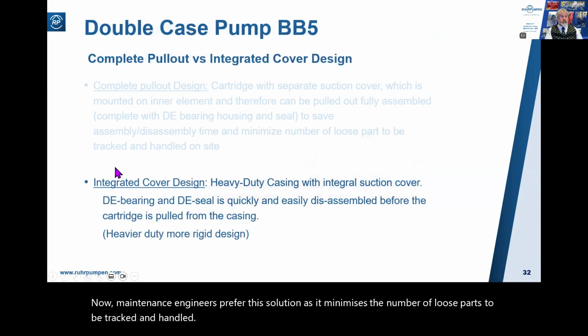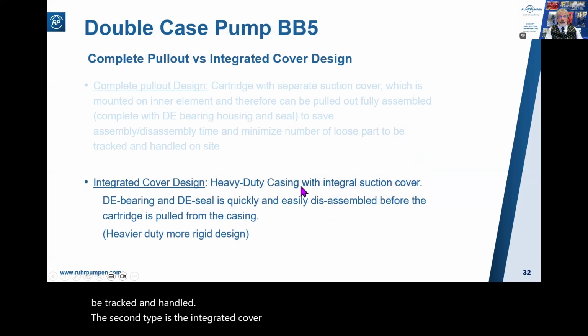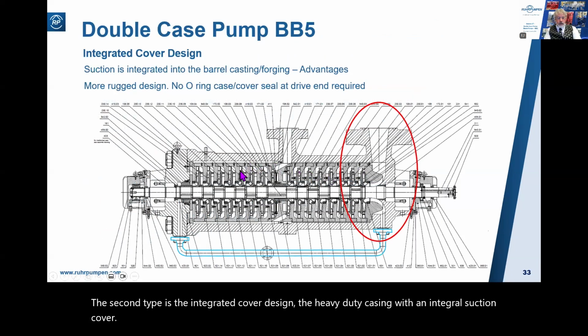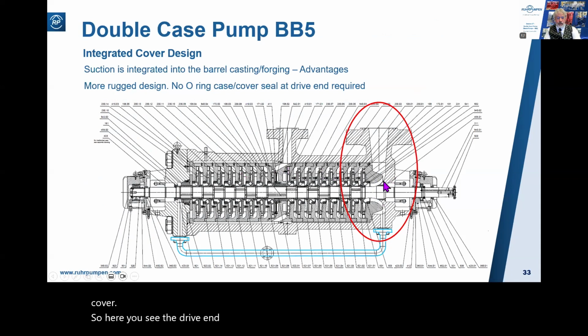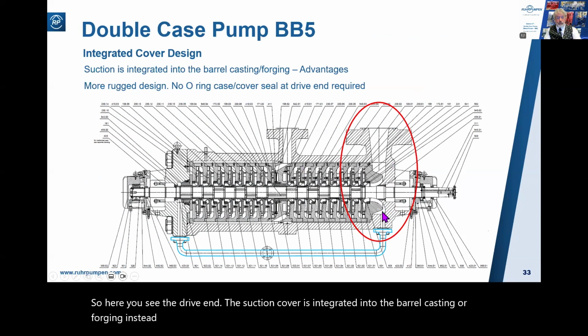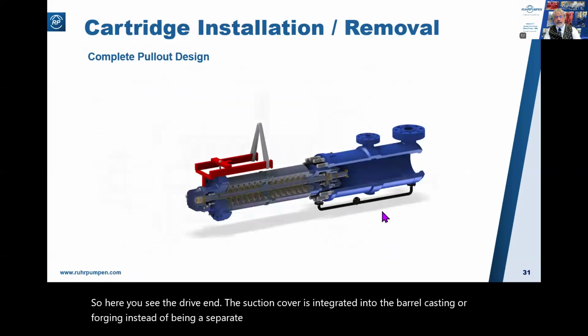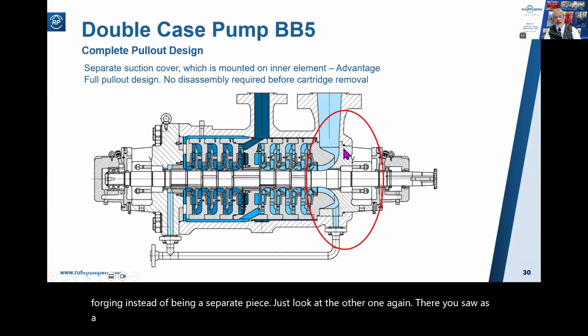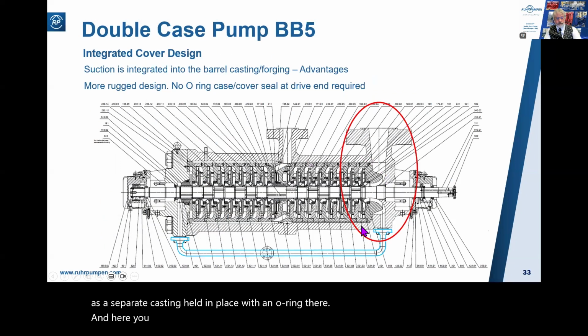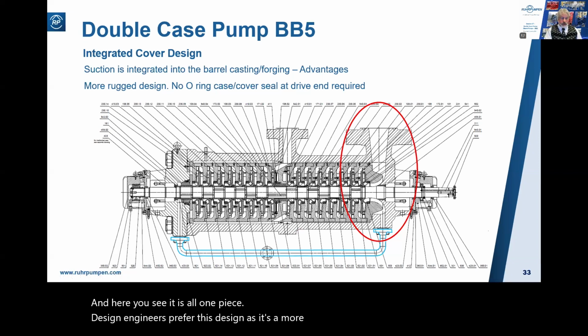The second type is the integrated cover design, the heavy-duty casing with an integral suction cover. So here you see the drive end suction cover is integrated into the barrel casting or forging instead of being a separate piece. Just look at the other one again. There you saw it's a separate casting held in place with an O-ring. And here you see it is all one piece. Design engineers prefer this design as it's a more rugged, robust design. It also doesn't require an O-ring seal on the drive end.